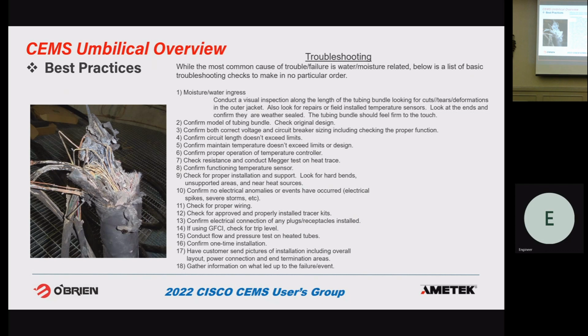And this is what happened. They had a short when they remade their connections up at the top, and it vaporized about a foot, the last foot of the tubing bundle. I mean, it vaporized it. You can't even see the bottom of the probe in this picture. Took out the probe. The probe just looked like a fire. It was all soot inside.